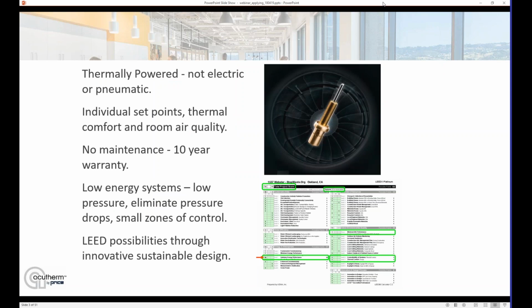Primarily, the diffusers we're talking about are thermally powered, meaning they're not electric or pneumatic, no wires, no tubing, powered by the temperature of the air, both the supply air and the room air. We do offer individual set points, leading to thermal comfort and better air quality in the rooms. They've been proven to be very robust over the years. We have really no maintenance requirement on them, other than to keep them clean for presentation purposes, and a 10-year warranty on the thermally powered ones. I'll throw in there, we also have electric diffusers as well, and we will touch on those at some point.